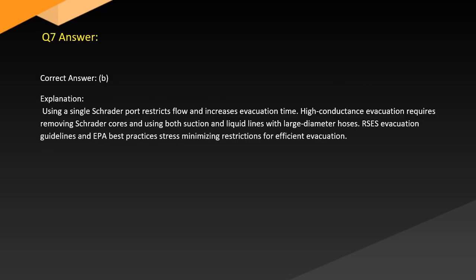Answer. Correct answer: B. Explanation: Using a single Schrader port restricts flow and increases evacuation time. High conductance evacuation requires removing Schrader cores and using both suction and liquid lines with large diameter hoses. RSES evacuation guidelines and EPA best practices stress minimizing restrictions for efficient evacuation.